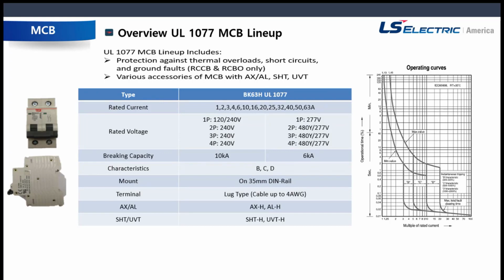UL 1077 lineup goes all the way up to 240 volt single pole, 480Y/277 4 pole. Same thing, also has B, C, and D trip characteristics and can be fitted on a 35 millimeter DIN rail. The lug terminal works on cables up to 4 AWG.